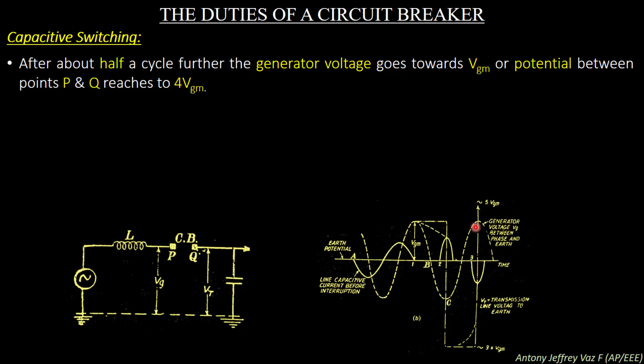Theoretically, the rise of potential to 7 VGM, 9 VGM, etc. will continue indefinitely, but it is limited due to corona loss and leakages. So this is a continuous process and it repeats, multiplying. This multiplication process continues indefinitely, but there is a stopping phenomenon because of the corona loss and leakages present in the power system. This capacitive charging current will discharge after a value of 9 VGM.